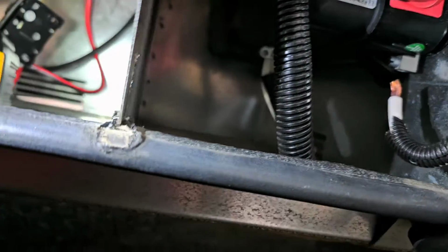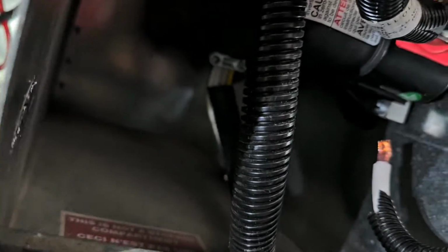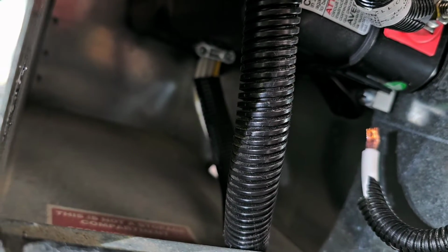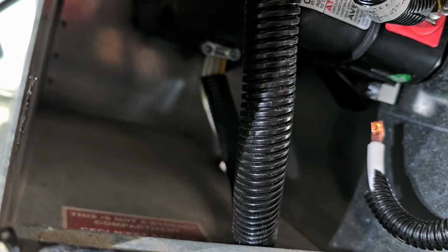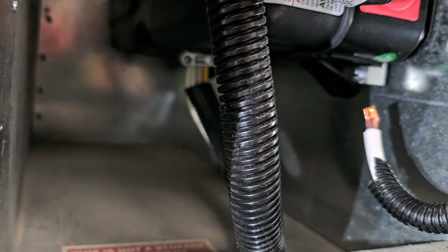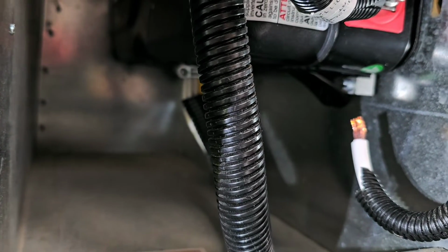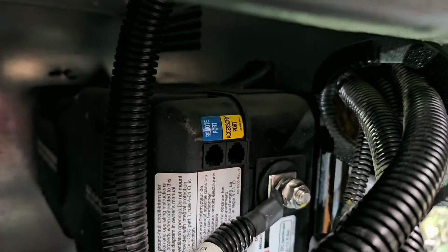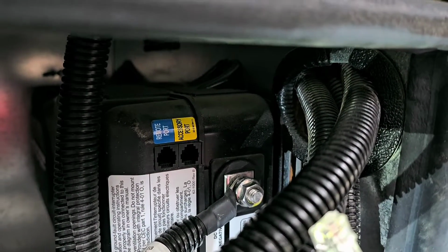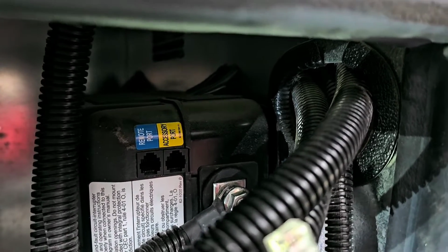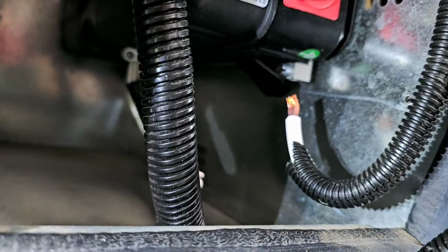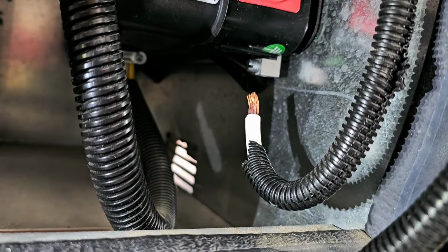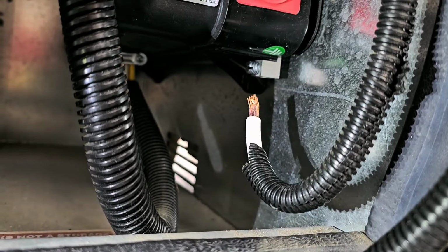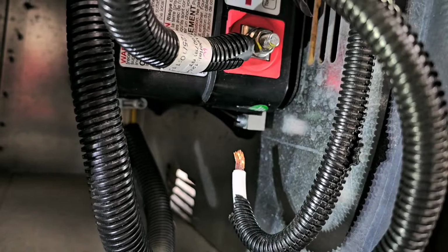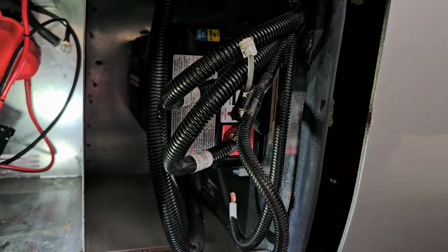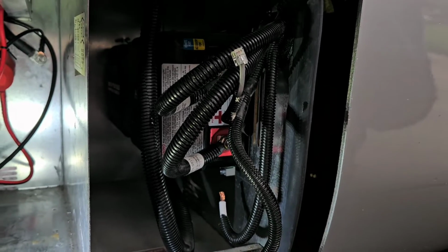Underneath — it's hard to see, but way under there — the yellow and white wires are the 120-volt wires. I'm going to need to pull this inverter off the wall to get to those. The inverter is mounted with 4 screws: two on top, and two more on the ears sticking out of the unit. So you remove those, and the whole thing falls out. That's how you get rid of the Magnum.